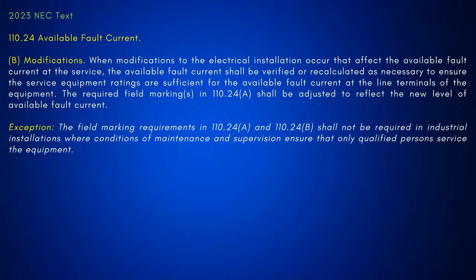For the available fault current, if it's at the service, you're going to want to get that from the utility. Well, no, I get that you're getting the available fault current, but I'm saying that once you're doing your thing, usually it's on the print, but let's just say they change from copper to aluminum or something. Is that something I could go in and just plug all those numbers into an app, get my available fault current, and label it at the gear?